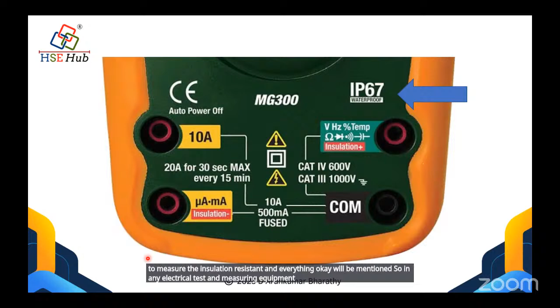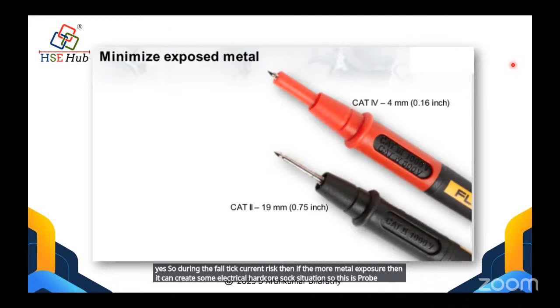Now coming to the probes, how to select the probe. This is one important practice - if followed, it will definitely avoid many accidents. This is called selecting the proper probe for category 4 and 3. You also have options now - you can add a cap on the category 2 probe and make it category 4, because the idea is to reduce metal exposure. Whenever we measure category 4, there is definitely a fault current risk, and if there's more metal exposure, it can create an electrical arc or shock situation. So the probe is also category rated.